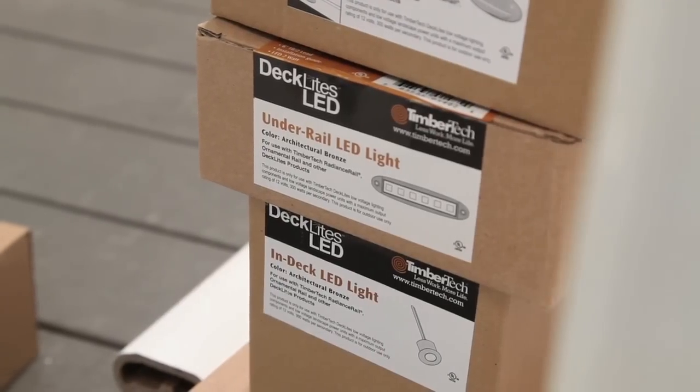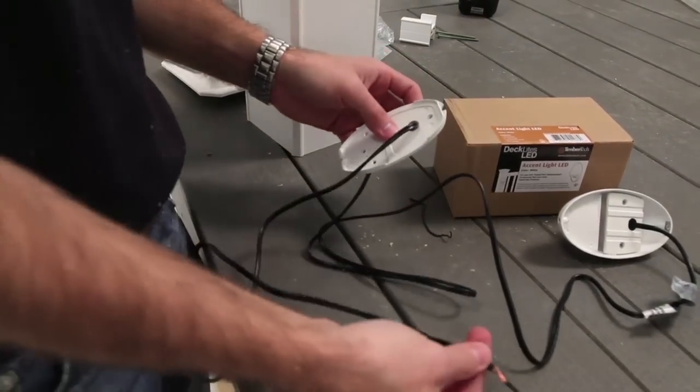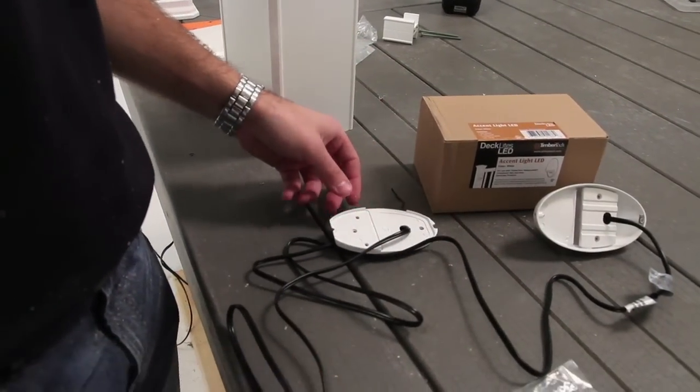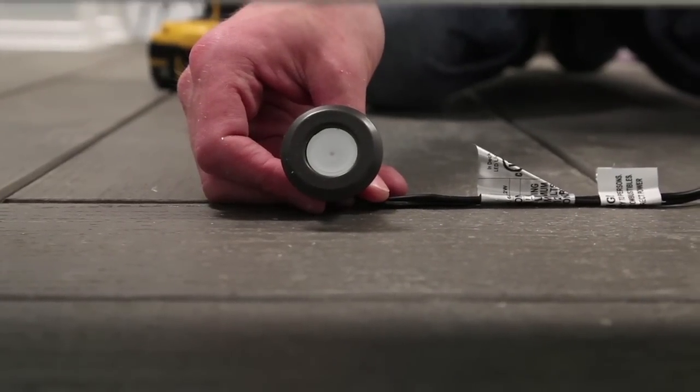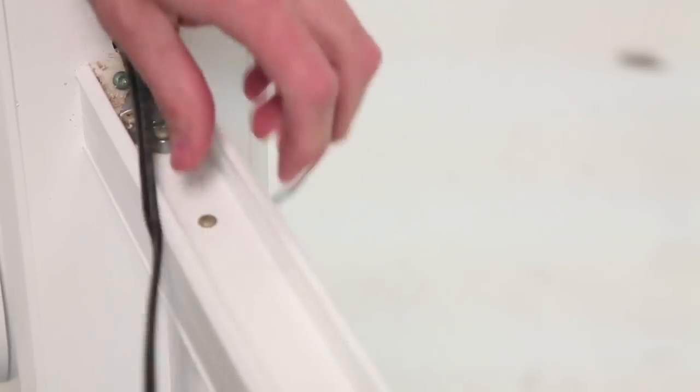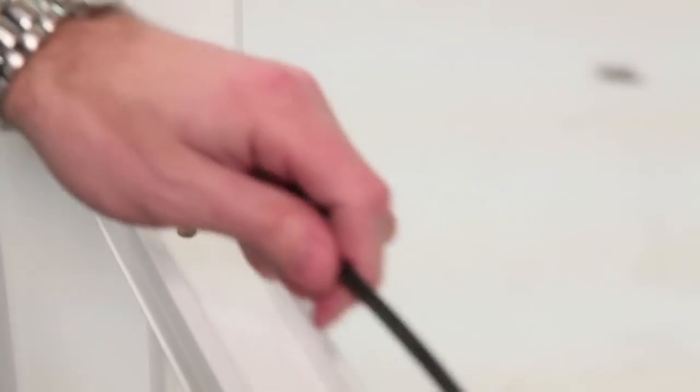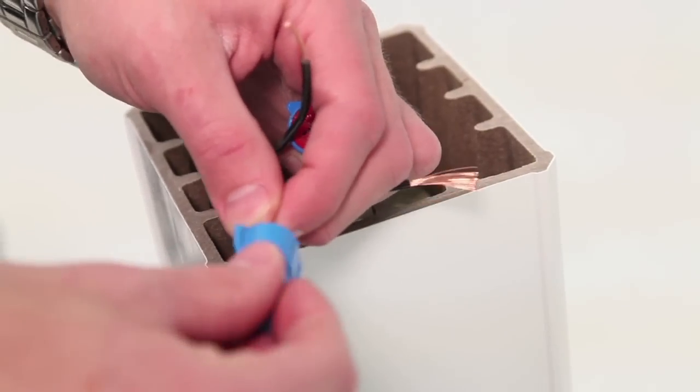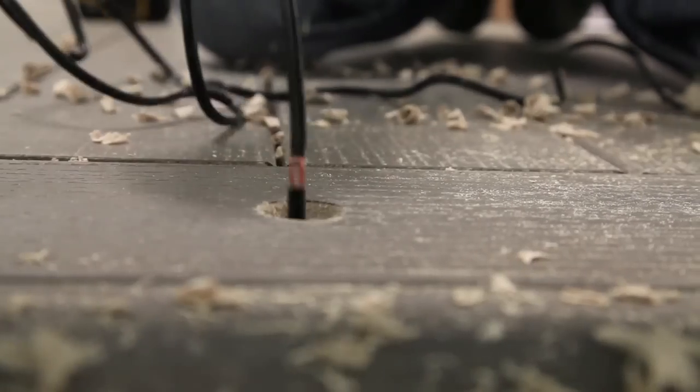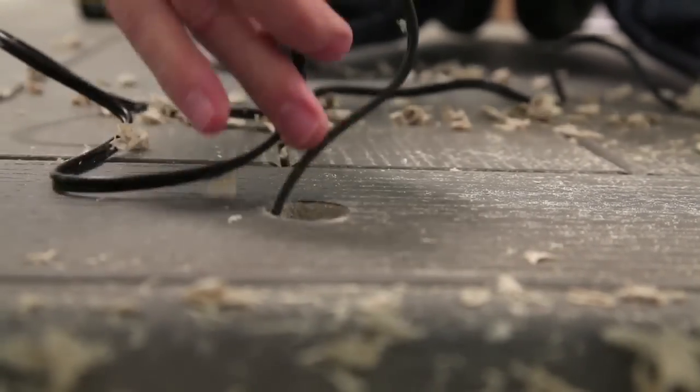The LEDs are built into the lighting fixtures and do not need to be purchased separately. When planning the layout of your lighting, refer to the installation guide to ensure that no more than 40 watts is applied to a single circuit and 90 watts is applied to a transformer.